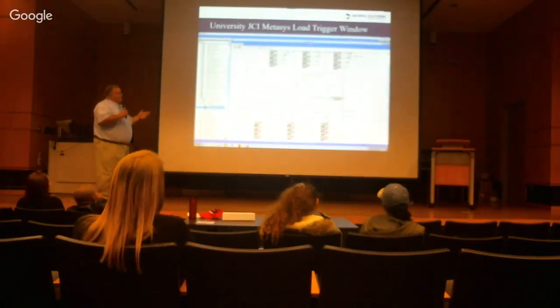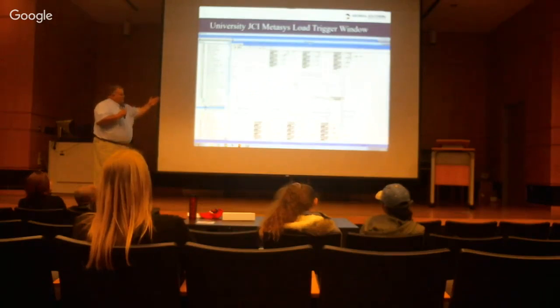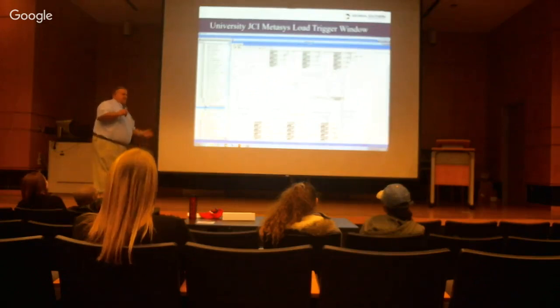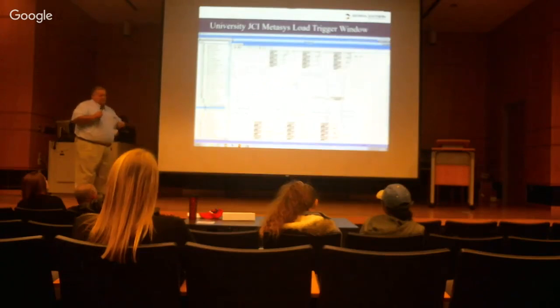This is our triggering system. We look at the amps that come into our system and correlate those amps to KW demand load on our whole campus. It refreshes about every 2 seconds. When we see all that, we get a global triggering demand. We do that July, August, September, and that keeps our rate tariff in line, produces that curve down below, saves a lot of energy and a lot of money.